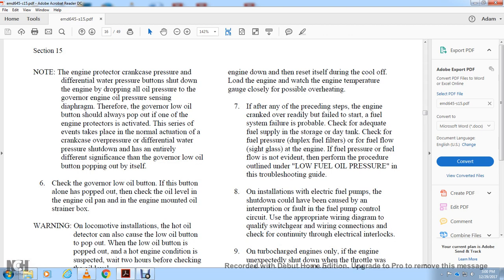If the engine cranked over but failed to start and a fuel system failure is suspected, check for adequate fuel supply in the storage or day tank. Check the fuel strainer, duplex fuel filters, fuel flow sight glass on the engine, and fuel pressure. If fuel flow is not adequate, follow the low fuel oil pressure troubleshooting procedure.